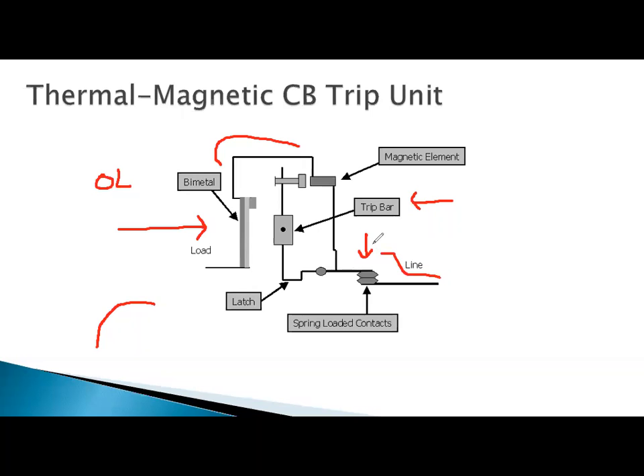up on an overload. Now, I have seen some circuit breakers on overloads that the bimetallic strip might not be working as good as we would like it. And so I have seen equipment melt because the bimetallic strip just did not do its mechanical job and get over there and open up that latch. But normally speaking, they do a great job. It could be that maybe we didn't maintain the circuit breaker properly or whatever, but on overloads, we are dependent on two pieces of metal, and when that current flows through there, that current is going to make one of those pieces bend and open the breaker up.